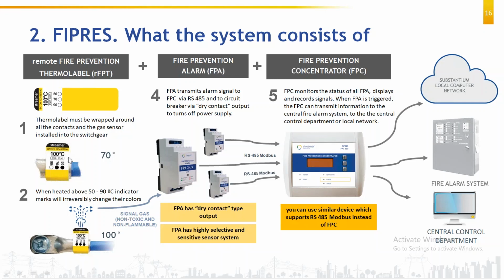Now, you have installed this particular sticker on a terminal block, on a cable lug basically, and the normal temperature of the terminal block was 70. So the sticker changed, and the 50 and 70 dots turned black. Now, for some reason, because of a fault or overload or any reason, if the temperature of the terminal increases beyond the set point of the sticker, which is 100 degrees in this case. We have stickers with different set points. In this case, it is 100 degrees. So if the temperature of the terminal block crosses 100 degrees, your sticker will release a signal gas. Okay, this signal gas is non-toxic, non-hazardous, and non-flammable.